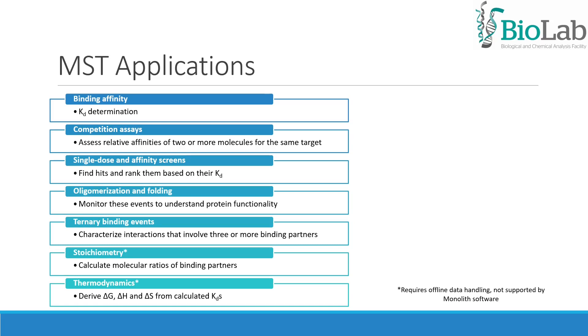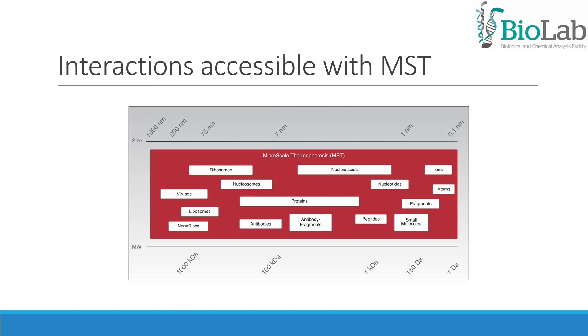The main applications of MST are binding affinity measurements, competition assays to assess relative affinities of two or more molecules for the same target, single dose and affinity screens, as well as studying oligomerization, folding, stoichiometry, and thermodynamics. The monolith can measure as little as the binding of a single ion or small molecule to a target, as well as the binding of large complexes such as ribosomes.